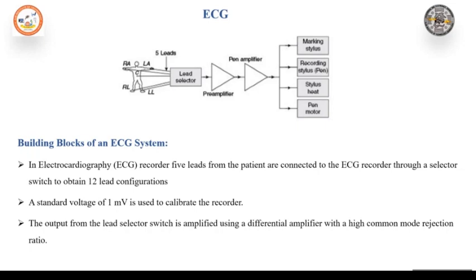A CMRR of the order of 100 to 120 dB with 5 kilo ohm unbalance in the leads is a desirable feature of ECG machines. In addition to this, under specially adverse circumstances, it becomes necessary to include a notch filter tuned to 60 Hz to reject hum owing to power mains. So the block diagram of ECG machines is illustrated in the diagram.